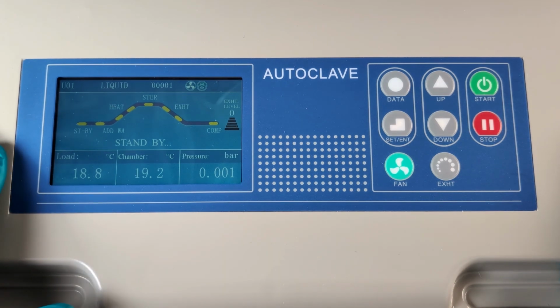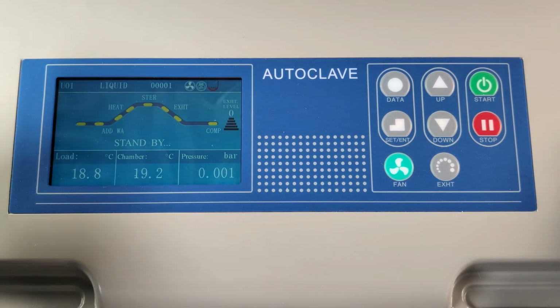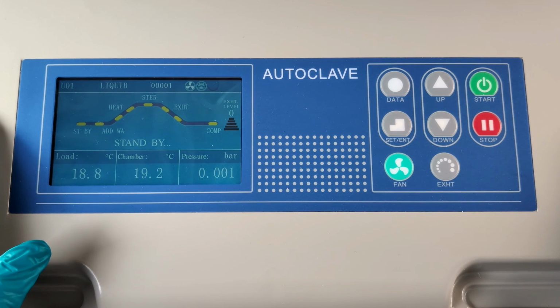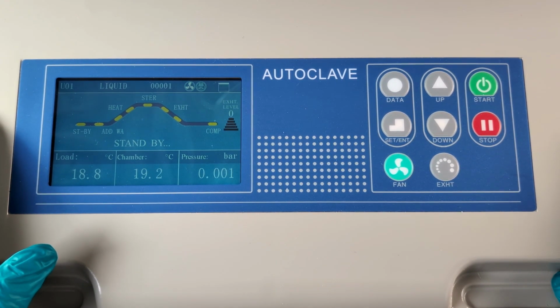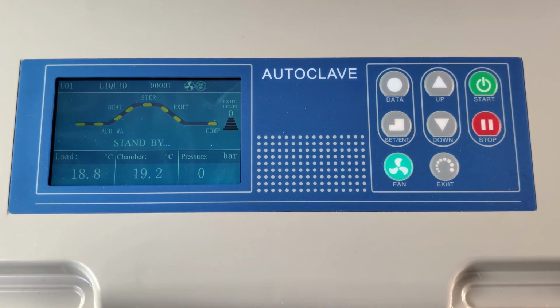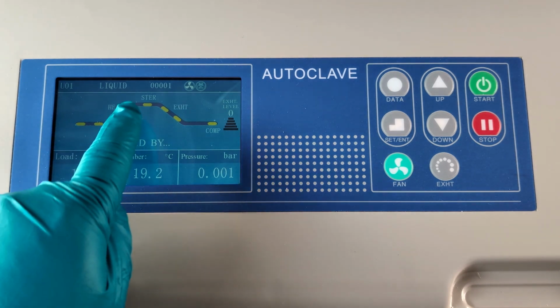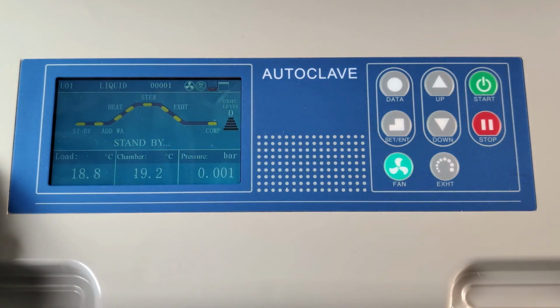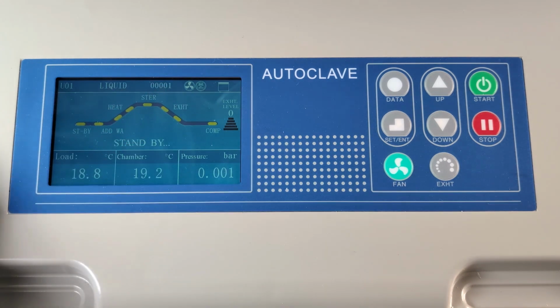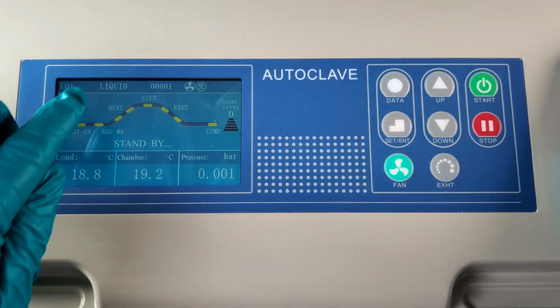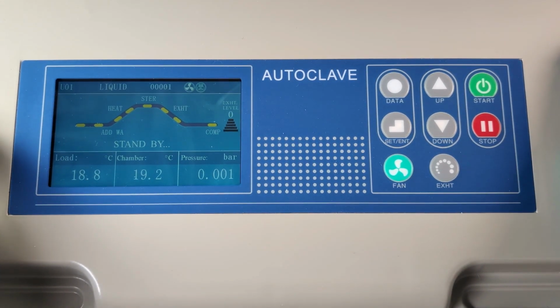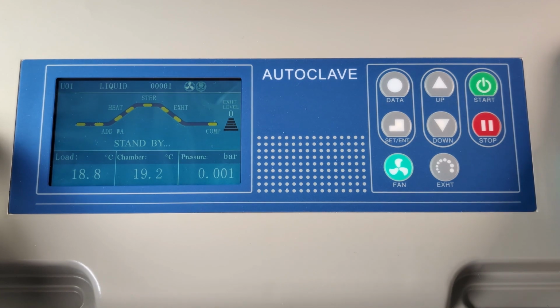Next, in the middle section of the screen, you have what looks like a temperature or pressure curve by time that you'd be familiar with if you've seen various sterilization curves. The reason for this is because it's very easy and very intuitive to see which part of the cycle you're actually on. You'll notice there are actually words either side of the curve, and these will change depending on the cycle that you're running, because different cycles need different phases.